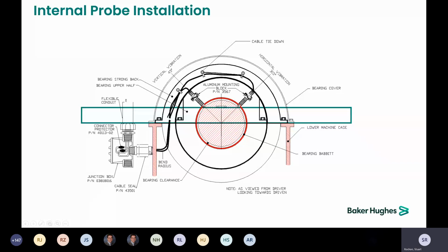Generally, it comes out through some sort of oil seal and into a junction box. If you are running into an issue where you have oil wicking through the cable, say you have a positive pressure casing, if you start getting oil in your junction box, we have a fluid lock cable that has silicone injected every 6 to 12 inches to act as an oil dam to keep that oil from wicking back up the insulation of the cable. So if you have that problem, switching to the fluid lock cable should eliminate that for you.